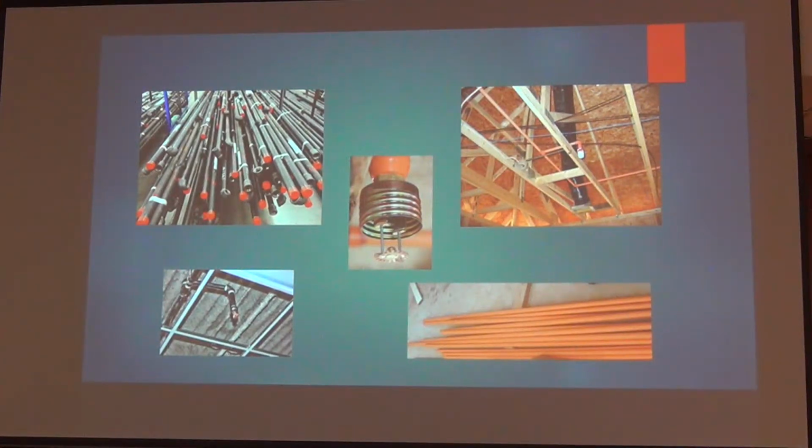That system underneath that building was designed for 8 to 10 heads to be activated at the same time to contain the fire. Remember, 13 is only to contain the fire. Will it put it out? Not on a lithium car. And that's what really bites about lithium, you know, so. Maybe. Yeah.